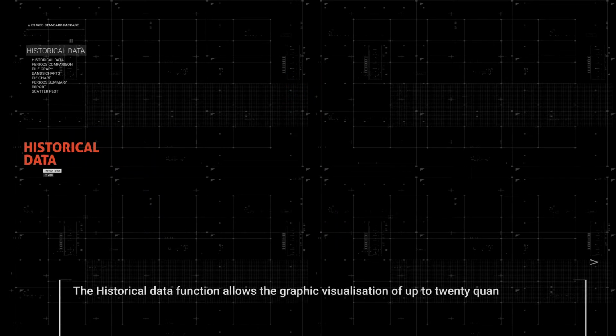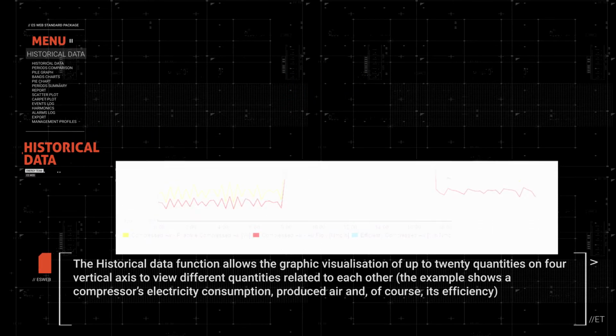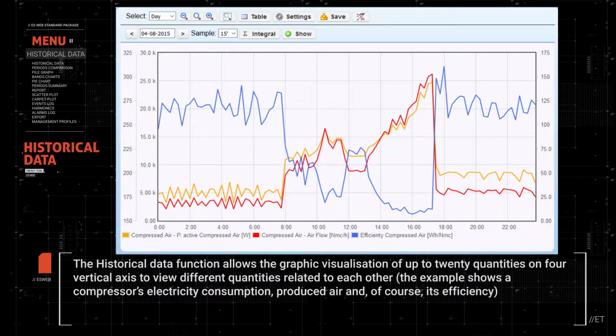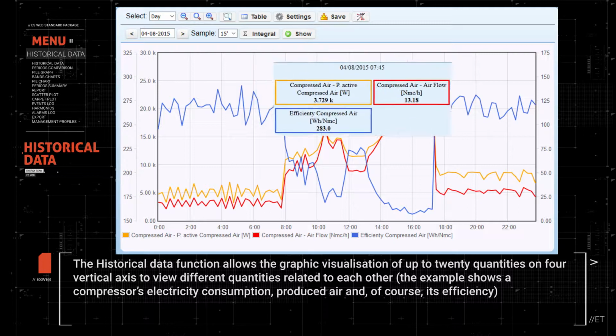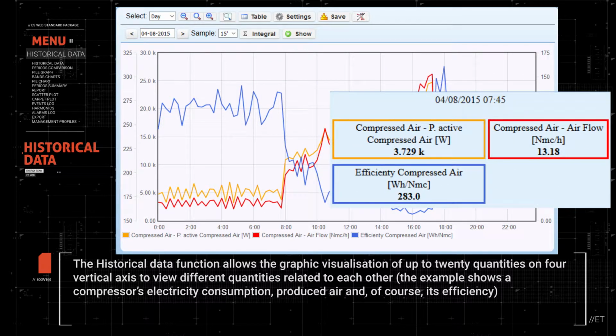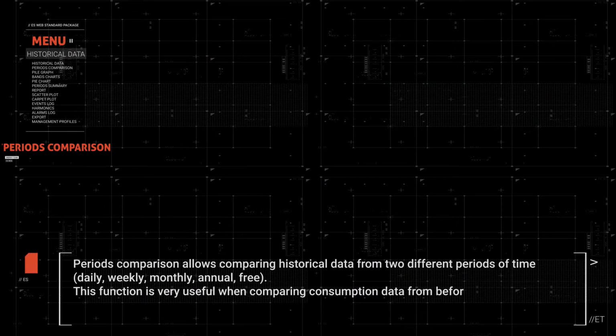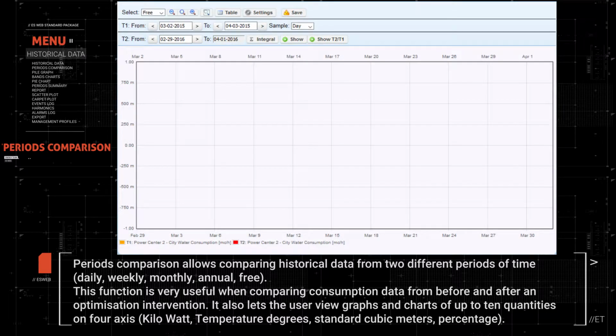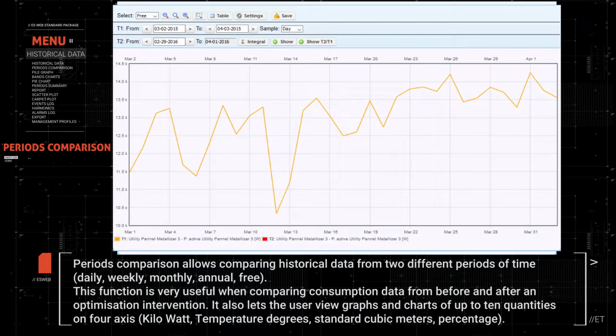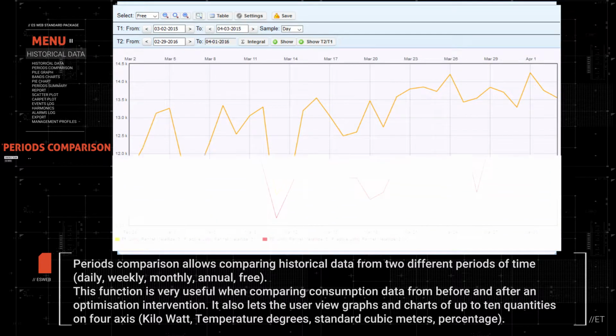The historical data function allows the graphic visualization of up to 20 quantities on 4 vertical axes to view different quantities related to each other. The example shows a compressor's electricity consumption, produced air, and, of course, its efficiency. Periods comparison allows comparing historical data from 2 different periods of time: daily, weekly, monthly, annual, free. This function is very useful when comparing consumption data from before and after an optimization intervention.